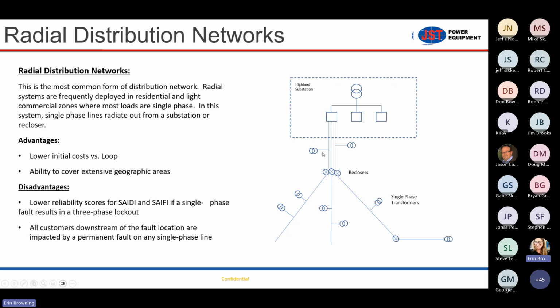You still have loads in between there, but you don't have any type of way to distinguish between momentary and permanent faults on those lines. So if you have a fault event on one line down here, which is a tree branch, a lot of times that circuit breaker is going to go into three-phase lockout. Not always, but some customers are in effect doing three-phase reclosing out of the substation, but you're still interrupting all three phases.